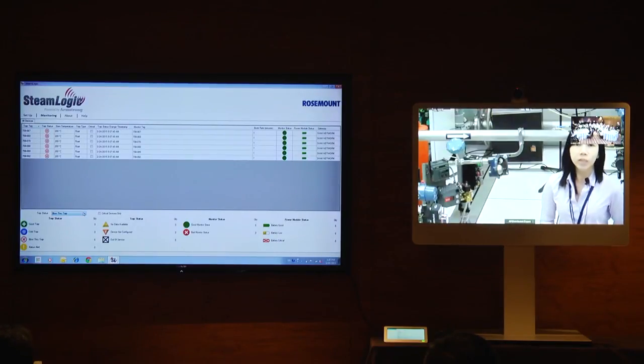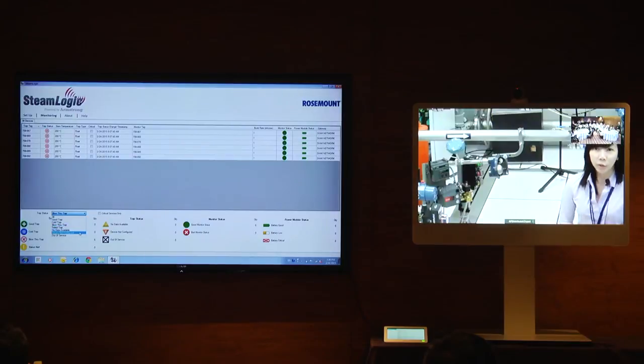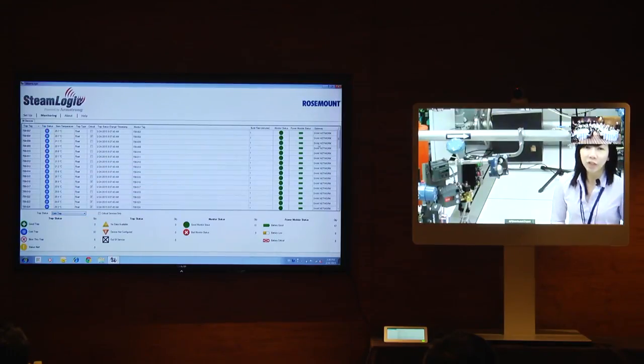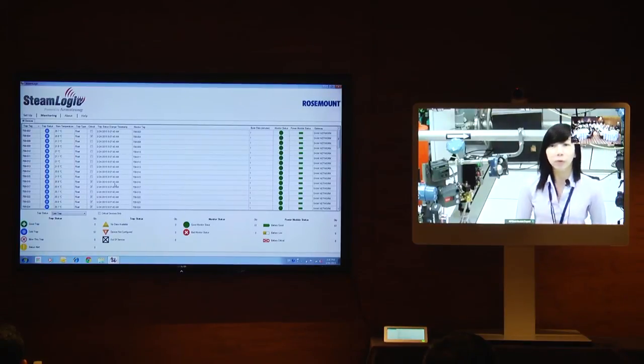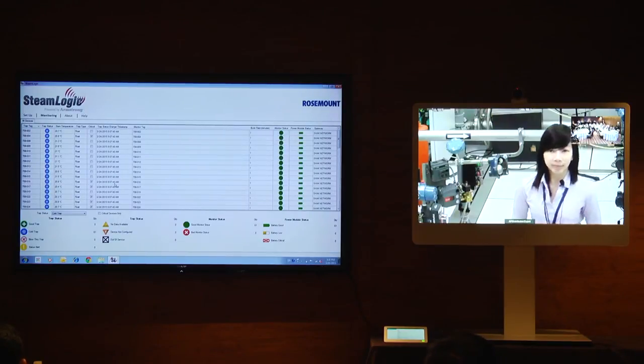In fact, a blowing trap means wasting energy. These traps need to be replaced. By detecting within minutes instead of weeks or months, a typical refinery can save up to $4 million a year on their energy bill. The traps flagged in blue are blocking traps. They reduce the heating efficiency and possibly cause equipment damage when water hammer happens in your plant. These steam traps also need to be replaced. That is how pervasive sensing helps to improve energy efficiency as well as reliability in your plant. Over to you, Jonas, if there are any questions.